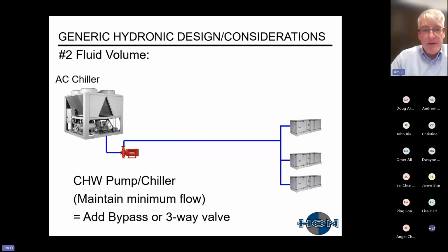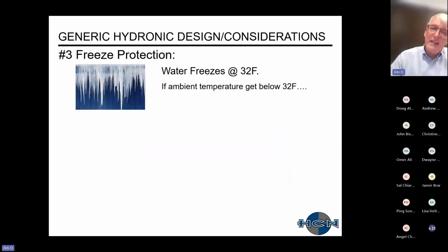All right. Other thing, just with fluid volume, is that the chiller has a minimum requirement for flow. So what you want to do is add a bypass or a 3-way valve. You don't want to put that in the mechanical room because once again you'll short cycle the water flow. You want to try to put it far away with a bypass, or it's easy enough to put in a 3-way valve for that.